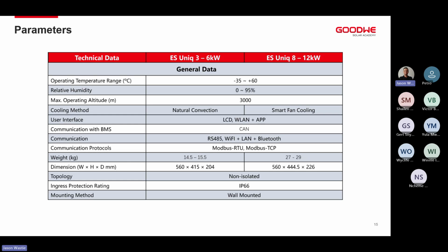All of our inverters come standard with a Wi-Fi LAN kit 2.0 communication dongle, and we use those dongles to make sure that we can connect it to the network so we can do remote configuration, remote troubleshooting, and remote monitoring of the plants. We can do it either via Wi-Fi or LAN, so running a physical cable, and we commission the systems using Bluetooth or the LCD screen built into the unit.